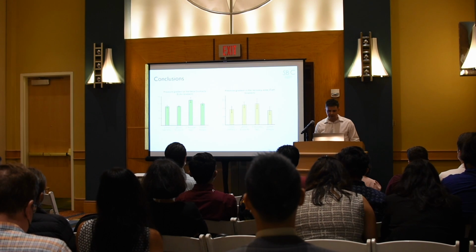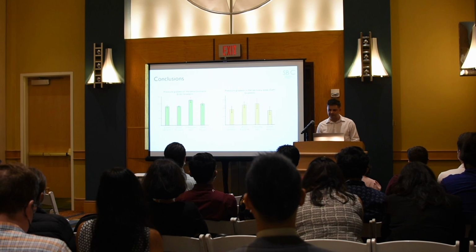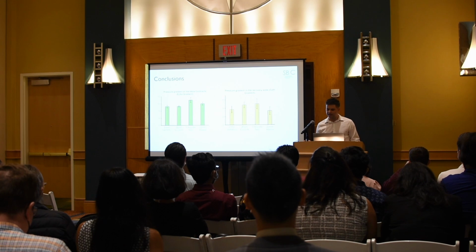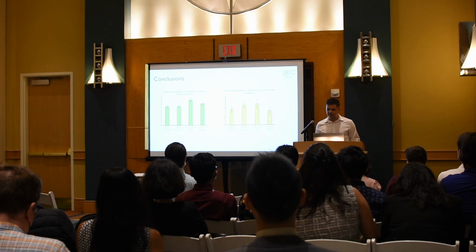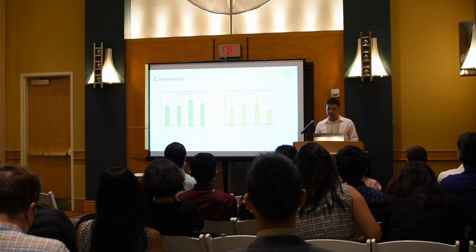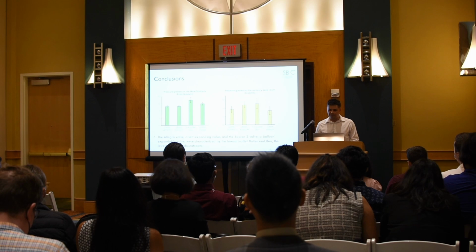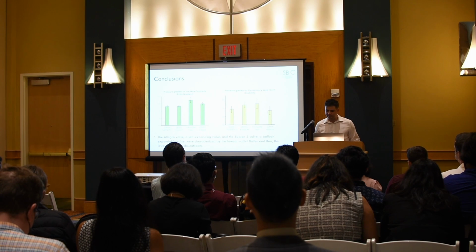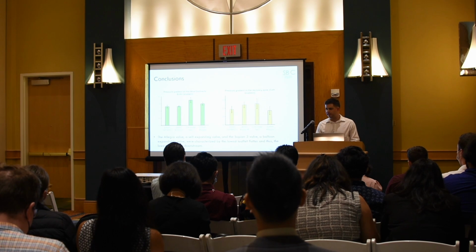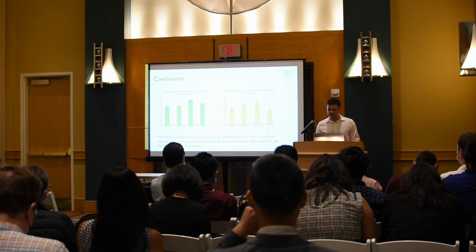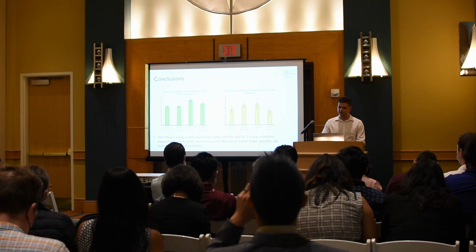In conclusion, the hemodynamics downstream of 4 transcatheter aortic valves, in which 3 of them were self-expandable valves, the Evolut, Acurate, and the Allegra, and 1 balloon-expandable valve, which was the Sapien 3, were evaluated in vitro under pulsatile conditions. And there was a distinct trend of performance obtained with each valve, independent of whether they are self-expandable or balloon-expandable. The Allegra valve, which is self-expanding, and the Sapien 3, which is balloon-expandable, were characterized by the lowest leaflet flutter, and thus the lowest turbulence downstream.